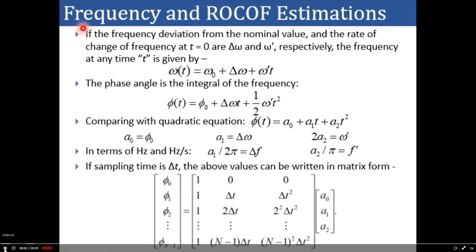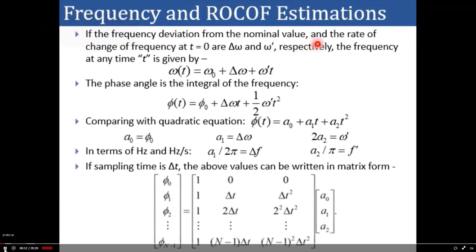Let us talk about the estimation of frequency and rate of change of frequency. If the frequency deviation from the nominal value and the rate of change of frequency at time t=0 is delta omega and omega dash, then the frequency at any time t can be given as: omega(t) = omega naught (fundamental frequency) + delta omega (change in frequency) + omega dash * t (rate of change of frequency component).